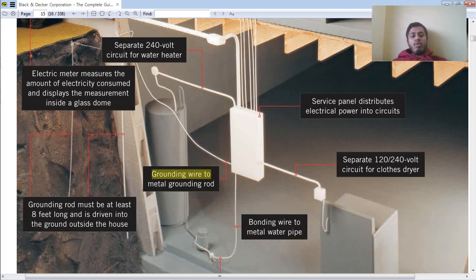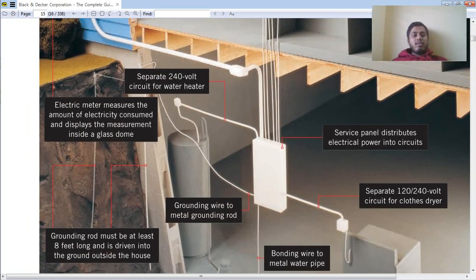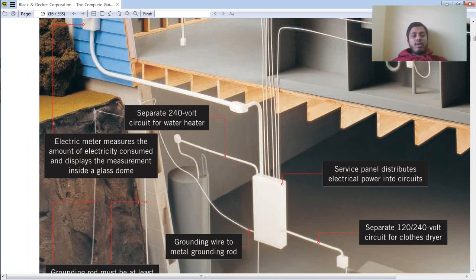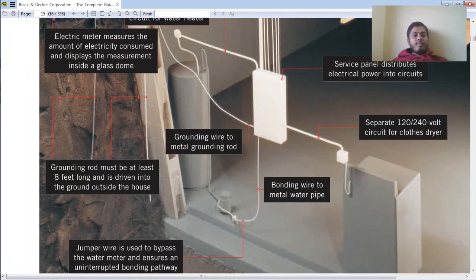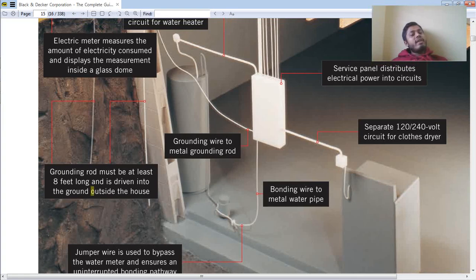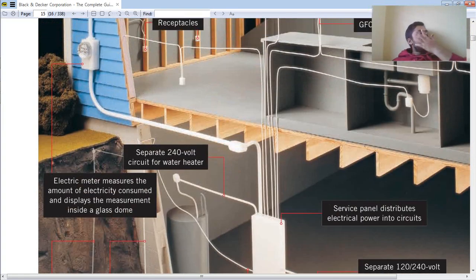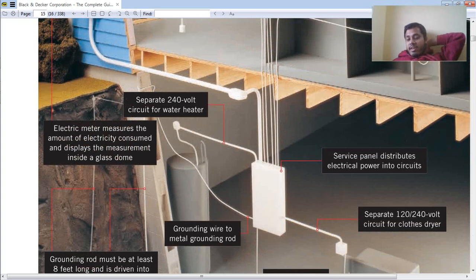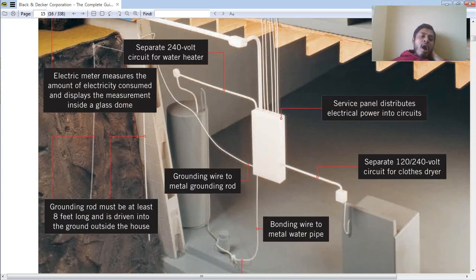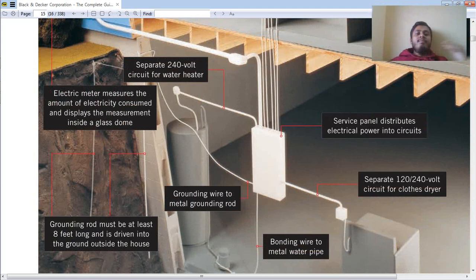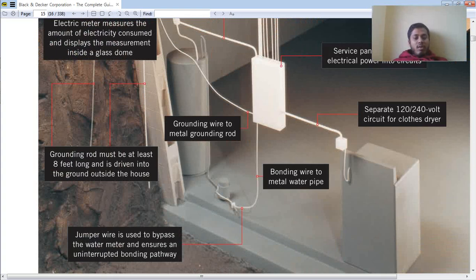Now, grounding wire to metal ground rod. This is the grounding, the earth ground. They use the ground wire and put it inside. The ground rod must be at least 8 feet long and is driven into the ground outside the house. So yes, earthing is done, and this should be 8 feet. This is the earth grounding.